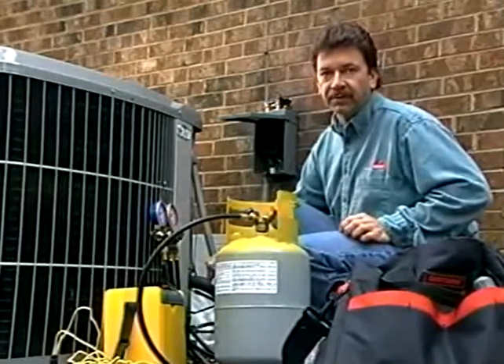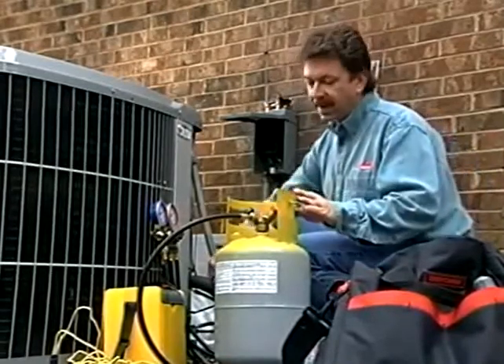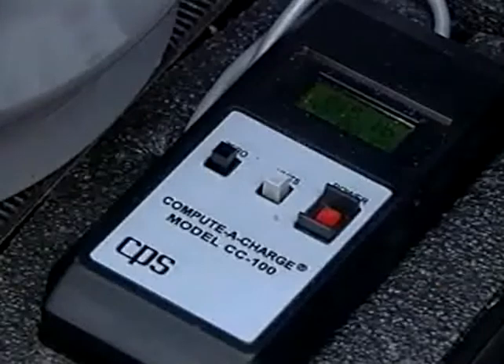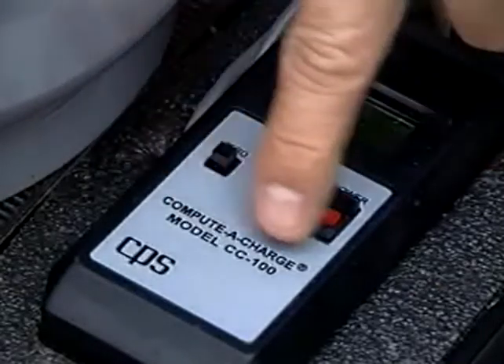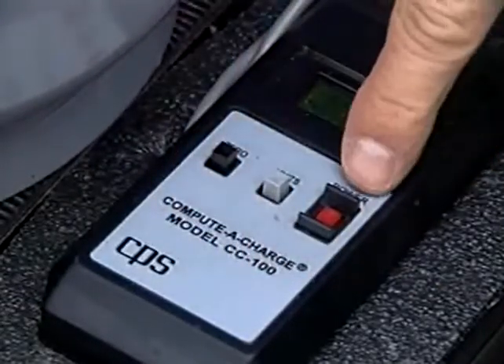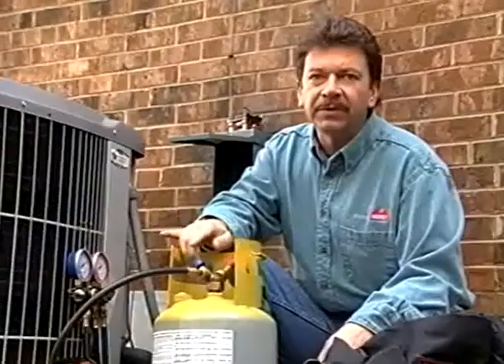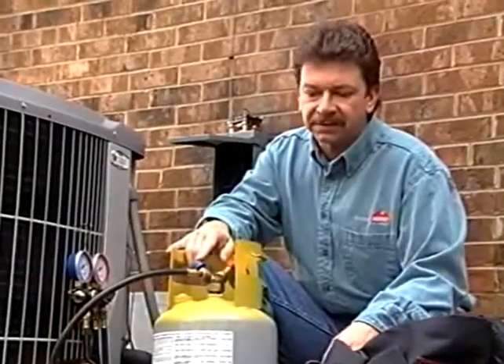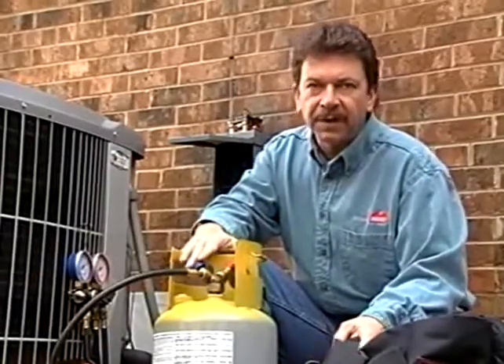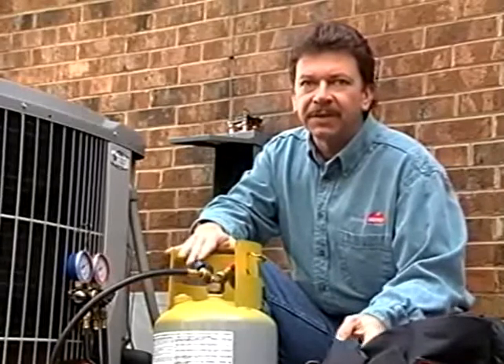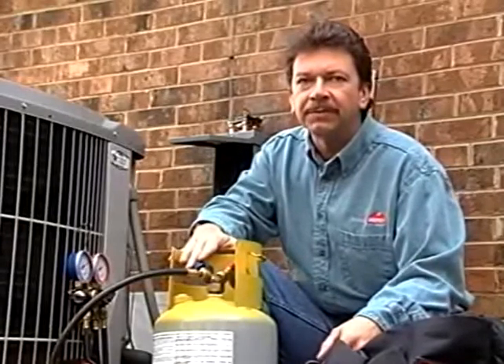or remove any refrigerant. If we were to add or remove refrigerant, definitely recommend you using a Compute-A-Charge and measure it to the closest ½ ounce. It's extremely critical that your system is charged to the ½ ounce. A variance in just a few ounces can mean a decrease in your efficiency and an increase in your power bill.